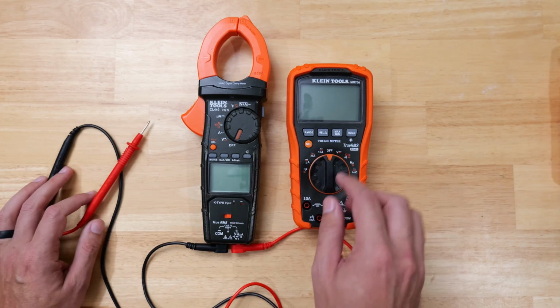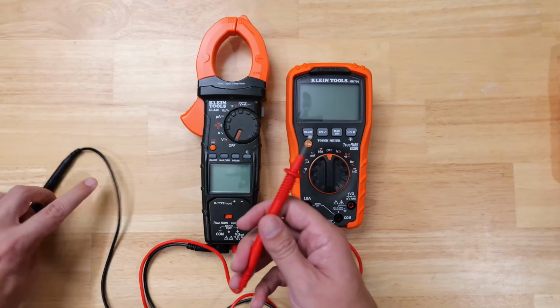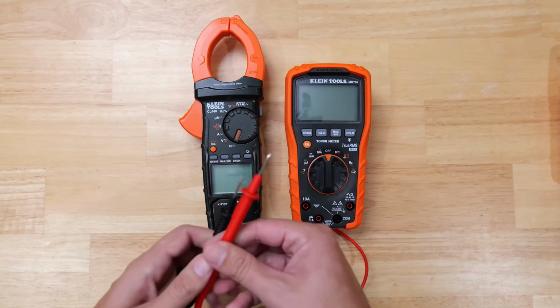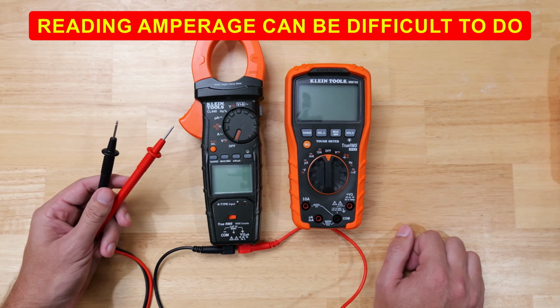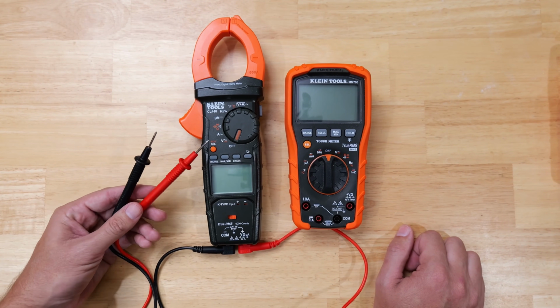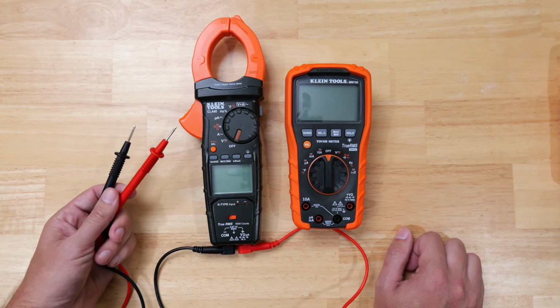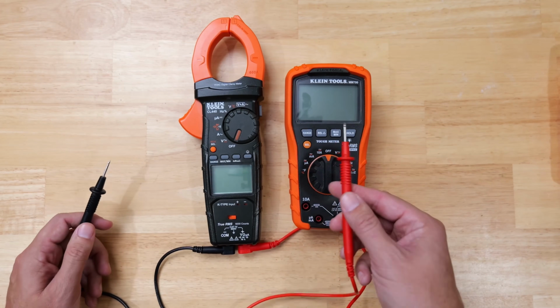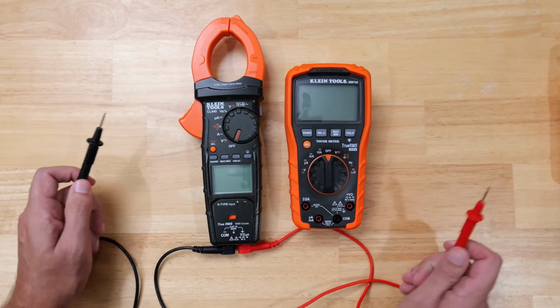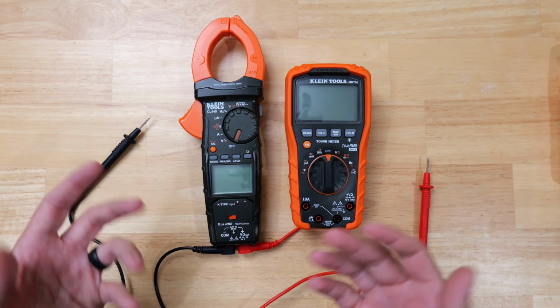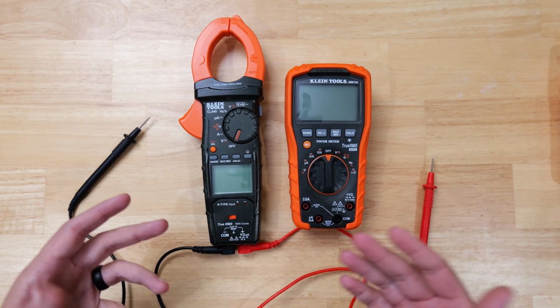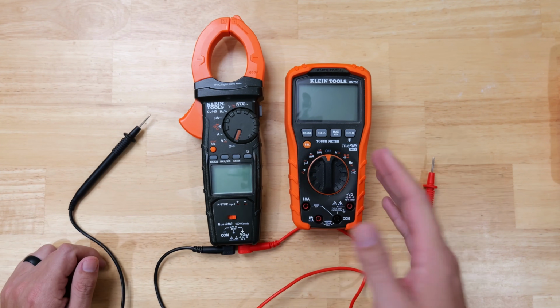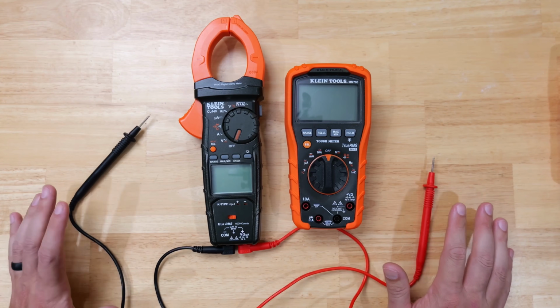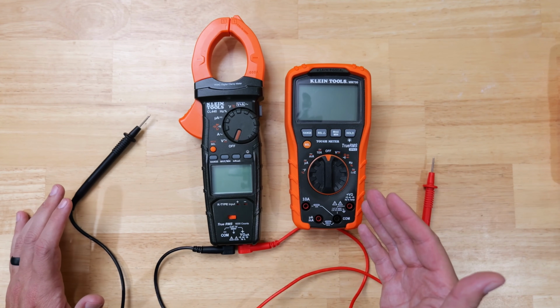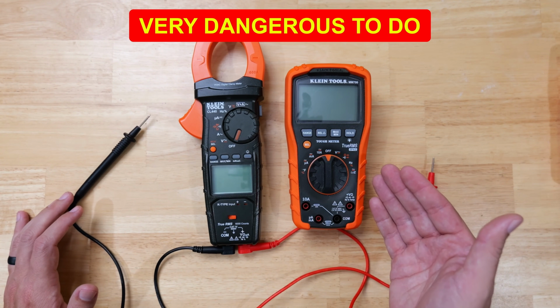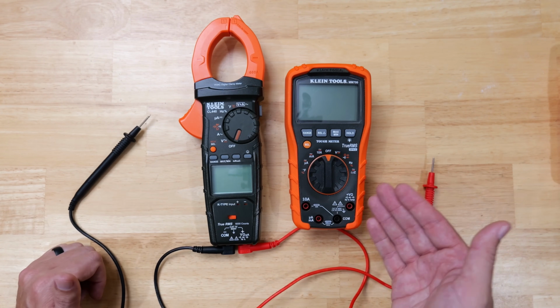If you're using a basic multimeter with probes, reading amperage can be incredibly difficult depending on the situation you're testing. It's not as simple as putting one probe somewhere and the other nearby. A lot of times you have to break the circuit and insert the multimeter in series so all the current flows through the meter. For many people this can be very complex and, in my opinion, also very dangerous, because to measure current you have to leave the power on.